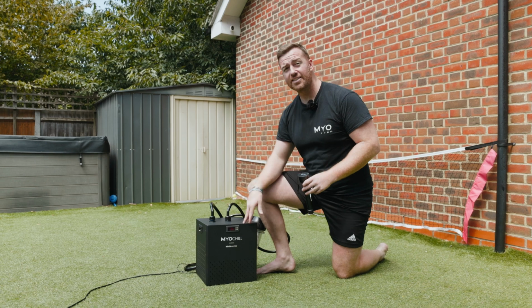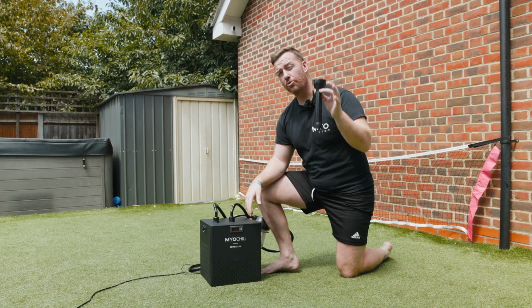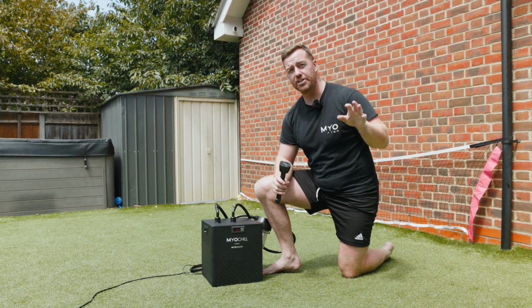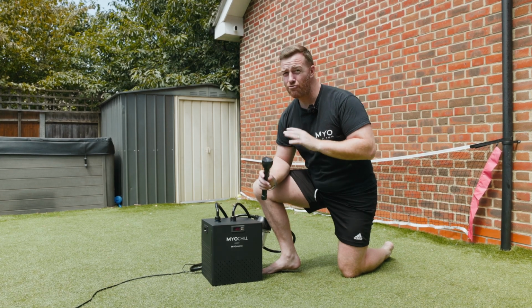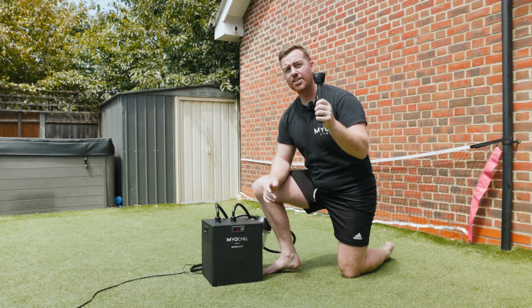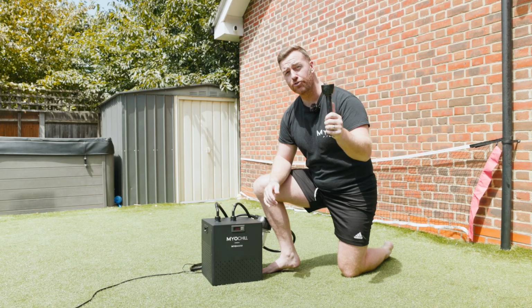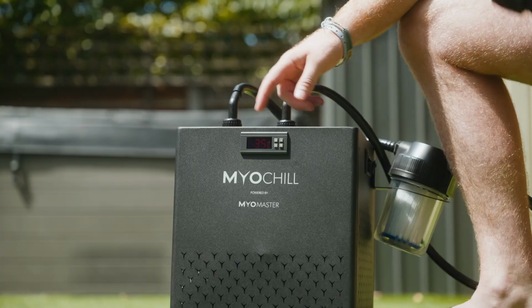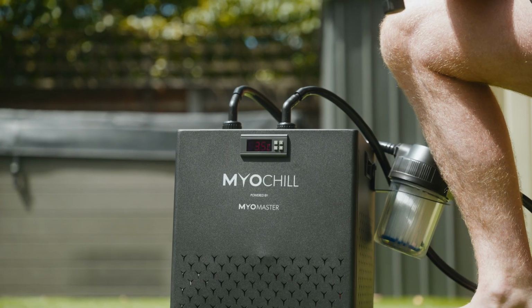So your chiller is giving you a different reading to what your thermometer is saying the real water temperature is. This is a really easy fix and very rare, but let's say that your ice bath says that it is 5.5 degrees, but your chiller is saying that it's 3.5 degrees. So there's a 2-degree variance.